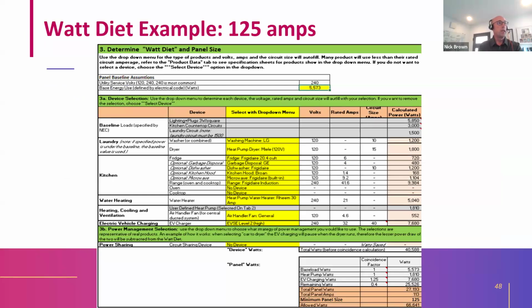This example is a 125 amp panel, and in my view it's got everything you could possibly need in an all-electric house. It's got a washer dryer, in this case a heat pump dryer, but there's room to put a bigger one if you wanted. It's got an induction range, a 30 amp 240 volt heat pump water heater, a heat pump for heating and cooling. This one has a 40 amp EV charging circuit, which, as Robert argued earlier, is probably more than most families need, still coming in at 125 amps suitable for this house.